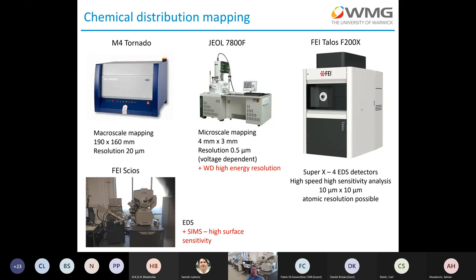What makes the centre specifically configured for looking at steels is our chemical analysis workflow, which allows us to map chemical distribution at high sensitivity from the tens-of-centimetre length scale all the way down to atomic level. We have three main systems: micro XRF for homogeneity in the tens-of-millimetre image field width range; an analytical FEGSEM from a few millimetres to tens of micrometres; and the TEM for all the way to atomic resolution. We also have a WDS, still needed for quantitative carbon profiles in steels and to resolve certain peak overlap issues.